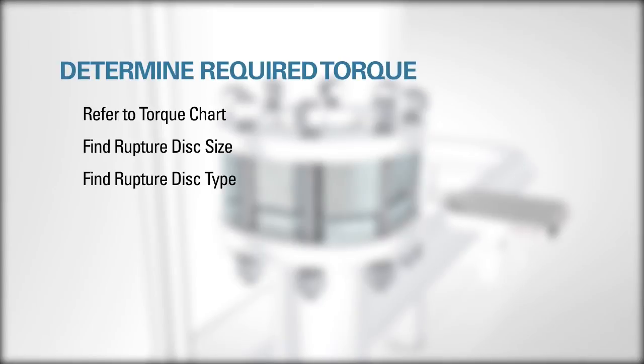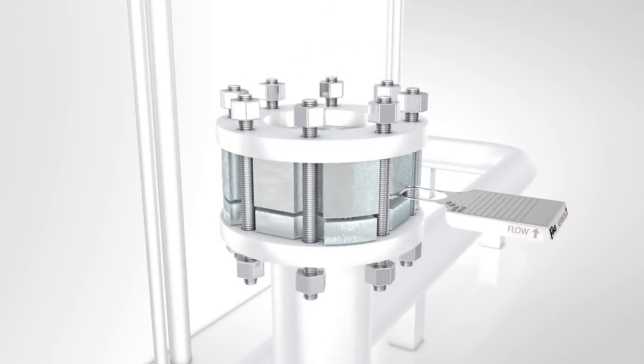To determine the required torque, refer to the appropriate stud torque chart included in the written installation instructions. Find the nominal rupture disc size and ANSI rating of your flange. Follow the row across the column that contains your rupture disc type to determine what is required in foot-pounds.